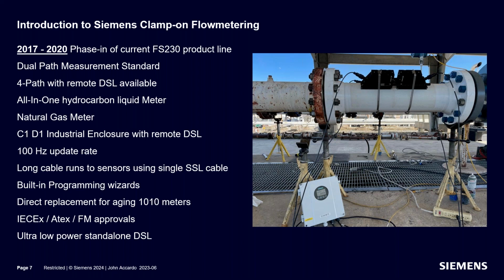The FS230 brought built-in programming wizards. It was a direct replacement for the aging 1010 and even 990 flow meters, if people still had them in service. So it's literally a device that you can unplug a 1010 from the wall, bolt up the 230, reconnect your transducer cables, and off you go, because it utilizes the same transducers. So it's capable of supporting both 990 and 1010 transducers. Those are the transducers that the FS230 is supplied with. They've just been relabeled as FSS 200 transducers, but they are the same transducers.